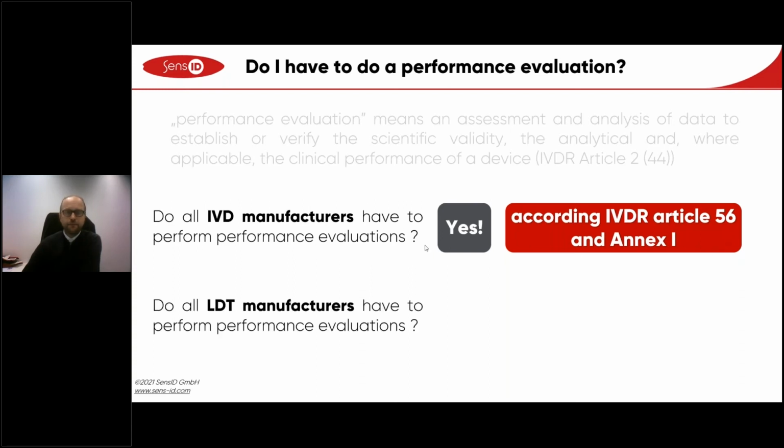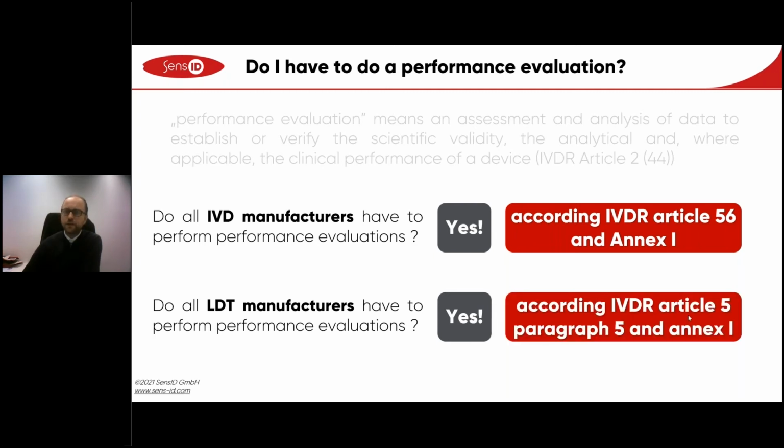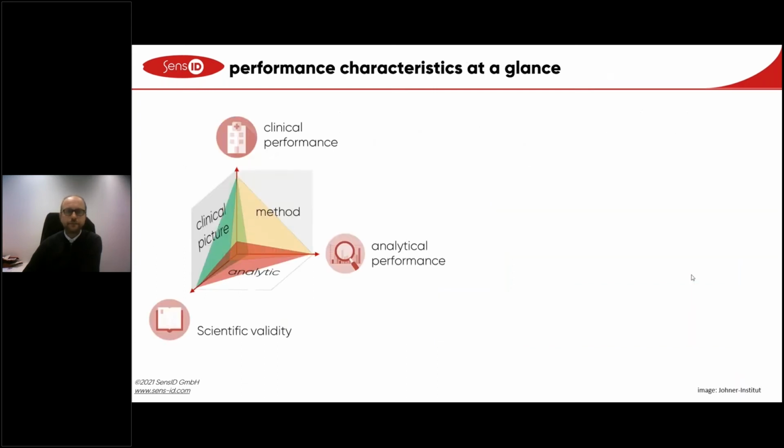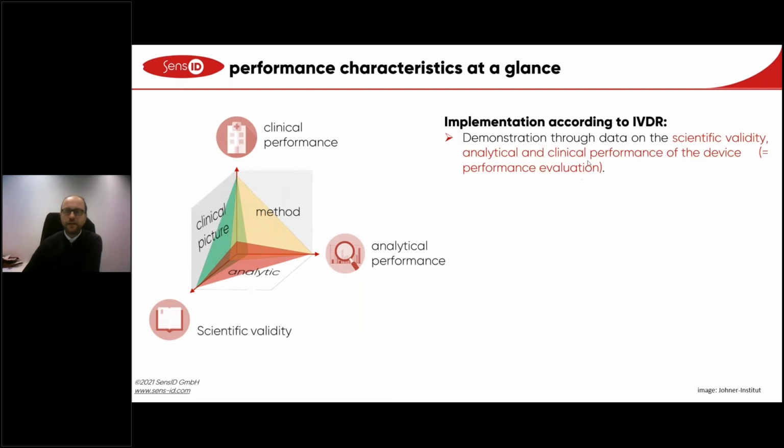And the second question would be if LDT manufacturers also have to do performance evaluations. And also here the simple answer is yes, but this time according to IVDR Article 5, Paragraph 5 and Annex 1. So here are the performance characteristics at a glance: clinical performance, analytical performance, and scientific validity. These taken together are meant to be the performance evaluation.